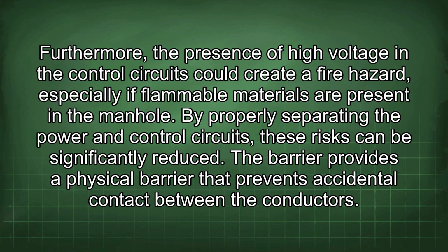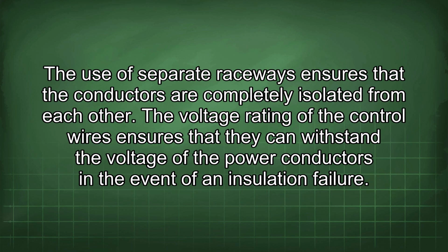Furthermore, the presence of high voltage in the control circuits could create a fire hazard, especially if flammable materials are present in the manhole. By properly separating the power and control circuits, these risks can be significantly reduced. The barrier provides a physical barrier that prevents accidental contact between the conductors. The use of separate raceways ensures that the conductors are completely isolated from each other. The voltage rating of the control wires ensures that they can withstand the voltage of the power conductors in the event of an insulation failure.